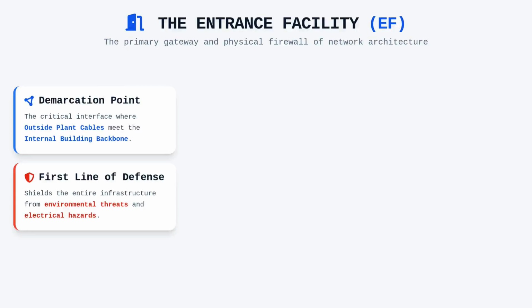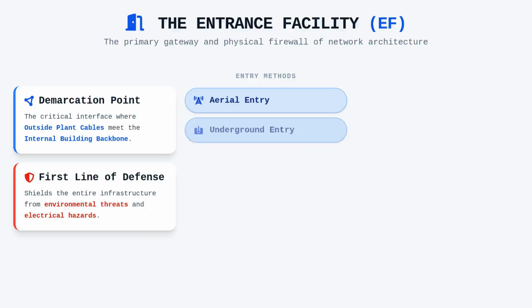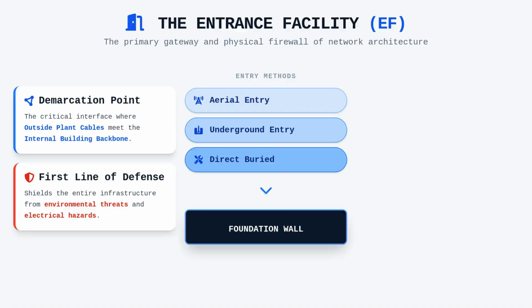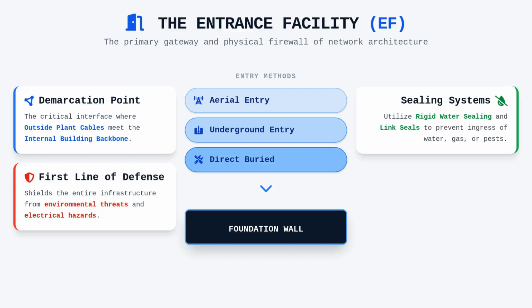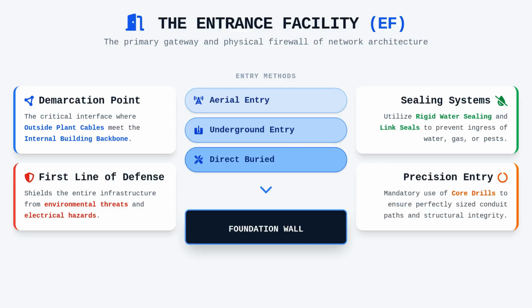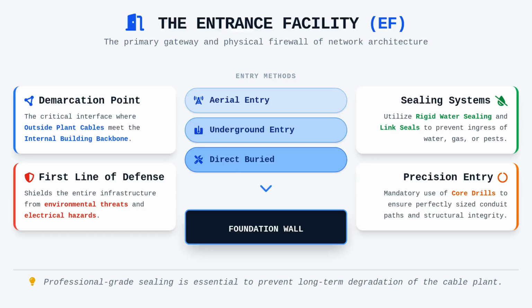You must consider the pathway of entry, whether it is aerial, underground, or direct buried, as each requires specific mechanical protections. When penetrating foundation walls, you are required to use rigid water sealing mechanisms and specialized transit systems that maintain the structural integrity of the wall while preventing ingress of water, gas, or pests. Using core drills rather than makeshift manual openings ensures that the conduit paths are perfectly sized and sealed with link seals, which are essential for maintaining the environmental envelope of the building. Think of this as the physical firewall of your network architecture, where professional-grade sealing prevents long-term degradation of the cable plant.